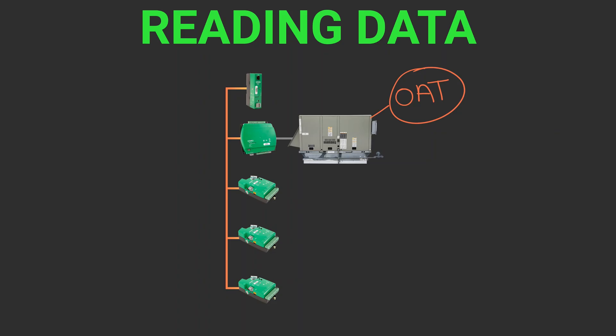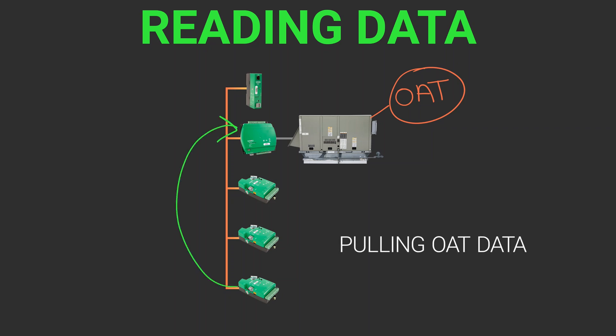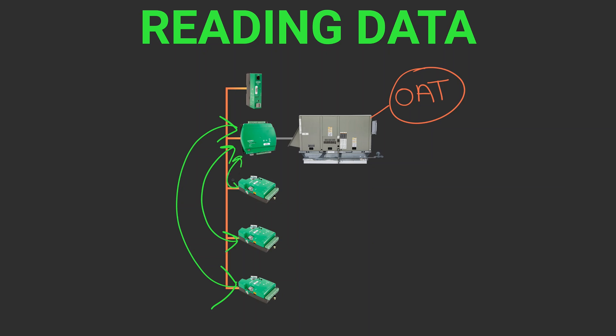When reading data, the controller generates a request for information from another device. Here, we are reading, or pulling, an outdoor air temperature from a sensor located on another controller. The request is generated and sent to the controller with the outside air sensor, which receives the request and replies with a message containing the outside air temperature value.